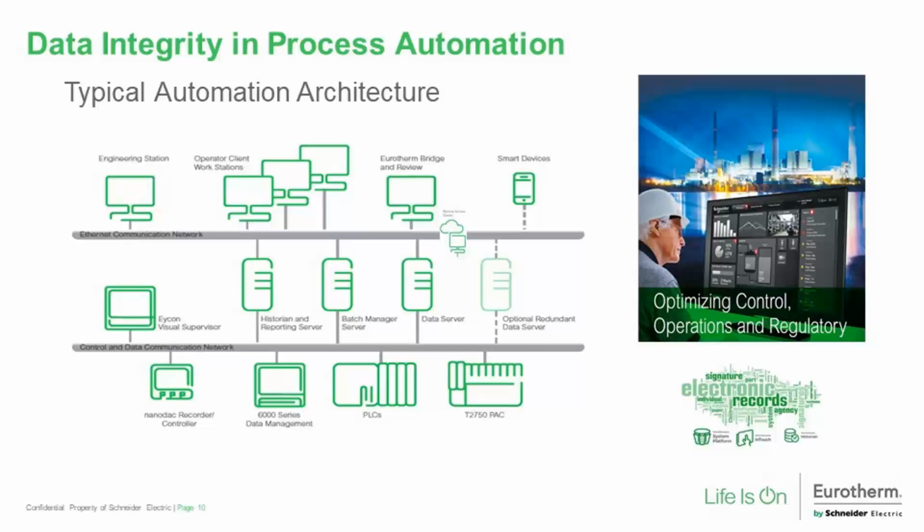That's where all your real-time data is coming in. That's where maybe your SQL database is constantly being updated. But off to the side, if you've got a batch process, you might have a batch server. The historian is key because that's where we get data integrity from saving all of our data in a very secure way. So all those things are just incredibly important in this design.